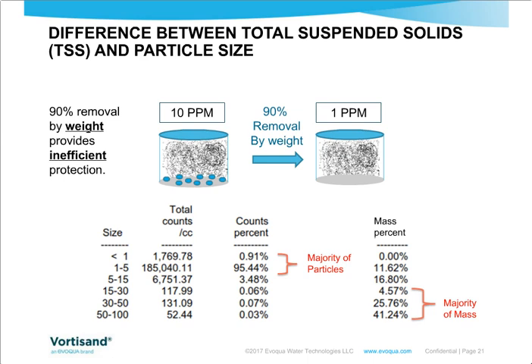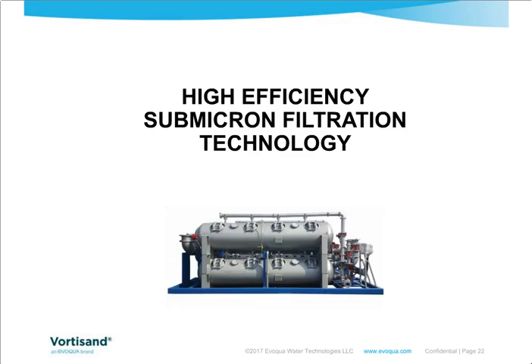And this table below shows you that 95% of the particles by size are less than 5 microns. And the majority of the mass, on the other hand, is large particles. So when you're removing by mass, it's a different removal technique than removing small, fine particulates, which is a very important part of understanding what technology to utilize. Now let's go into some more depth and explain an example of fine filtration technology utilizing high efficiency submicron filtration.